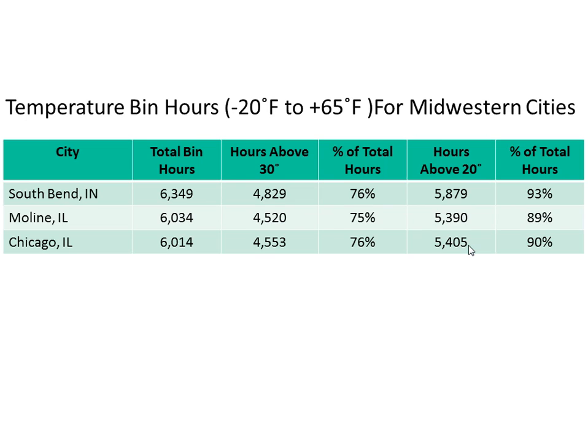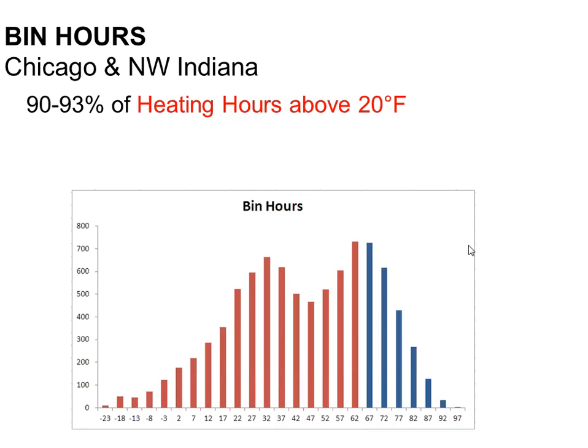And I'm not telling you to size it for 20 degrees, because when it's 0 degrees outside, your customers can get upset with you. So you still have to size it for 0 or -10 or whatever you do. But that doesn't mean we have to operate it there. There are going to be lots of hours that we don't need to be operating at full fire.